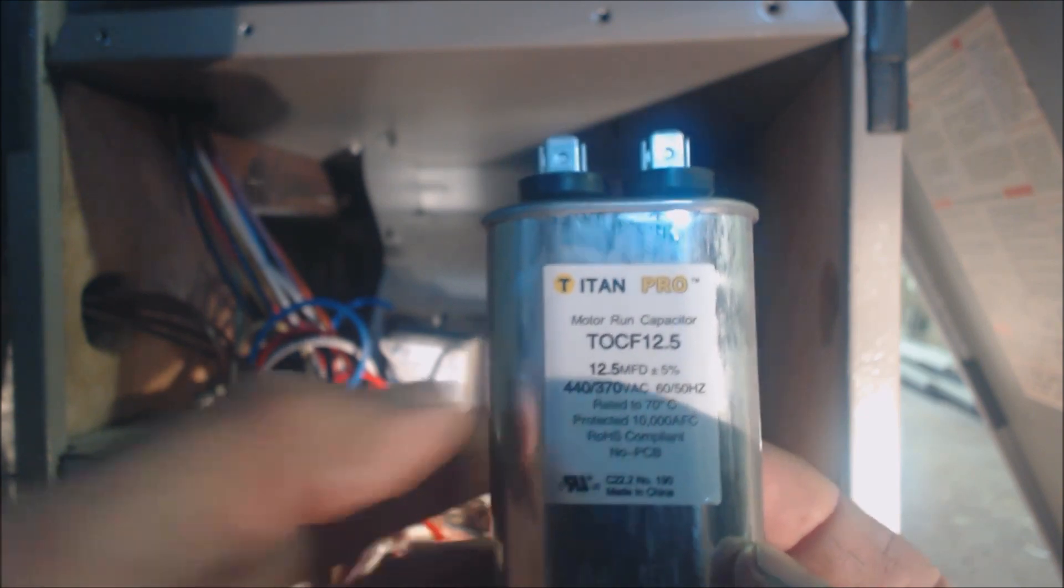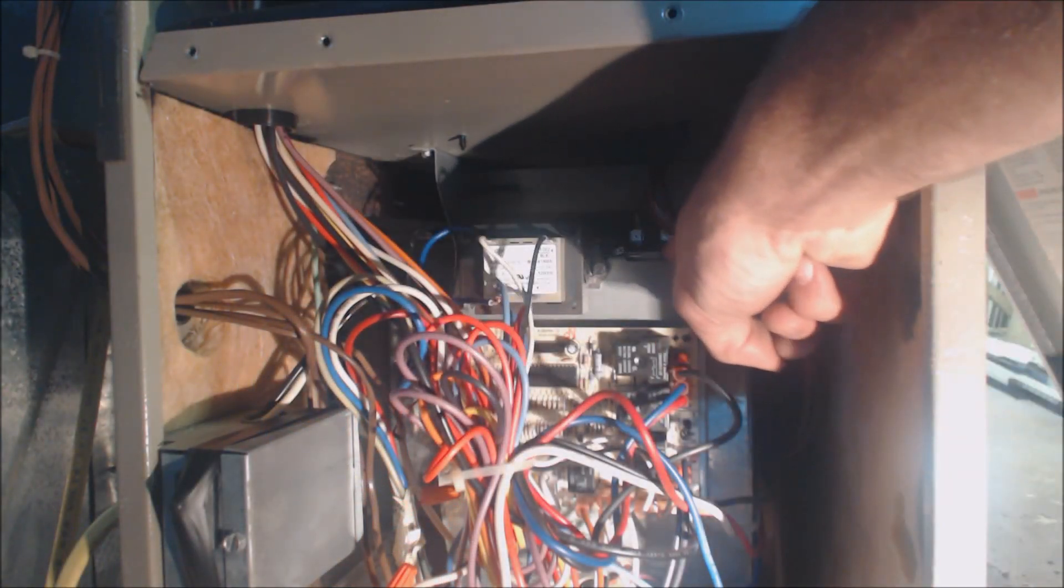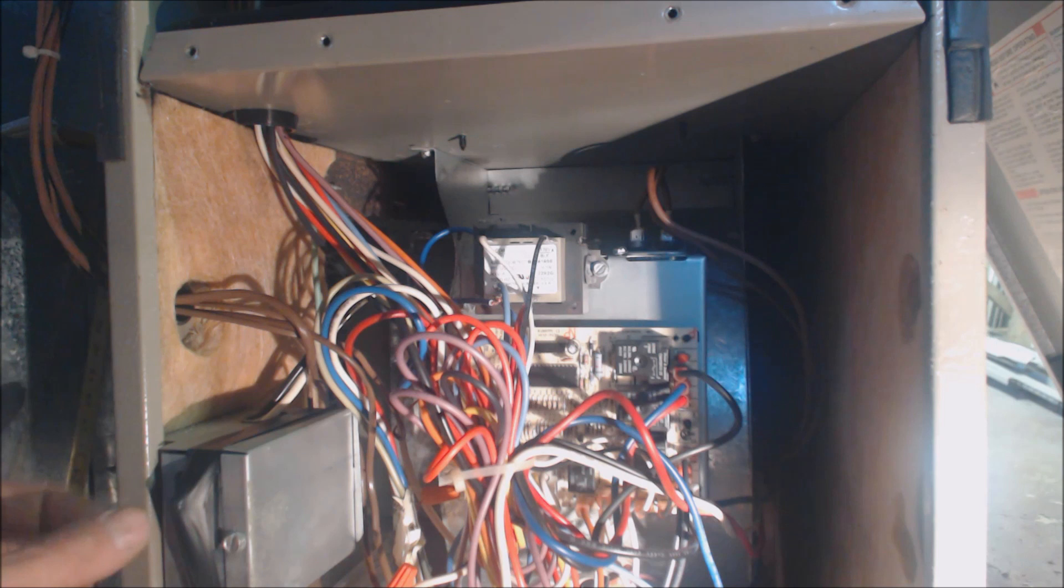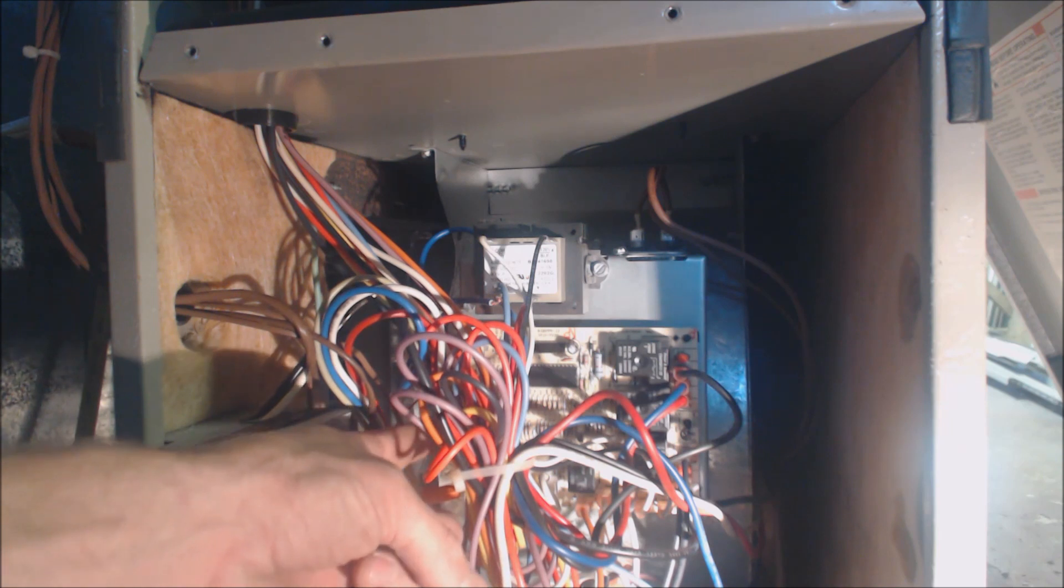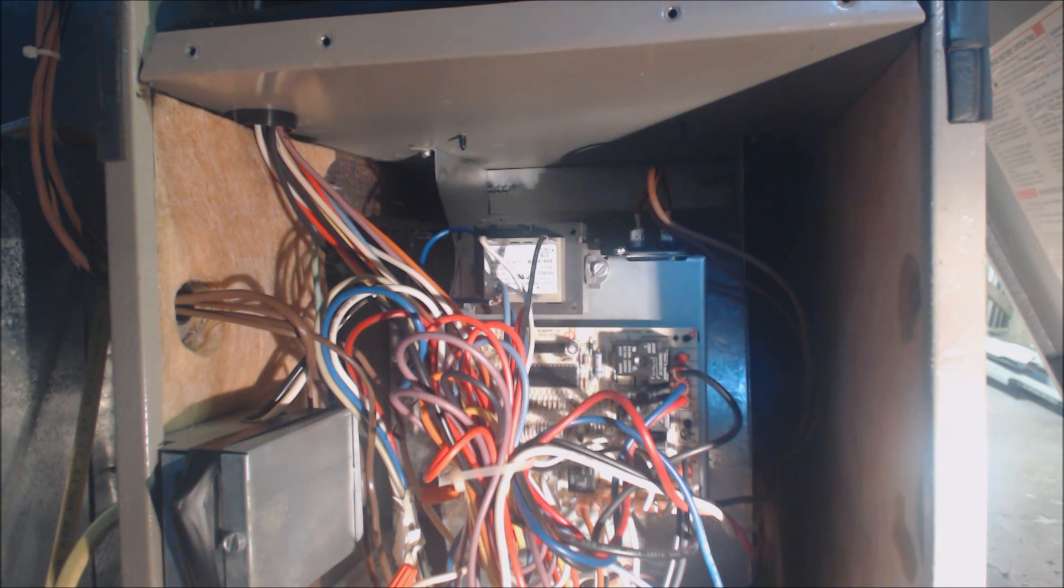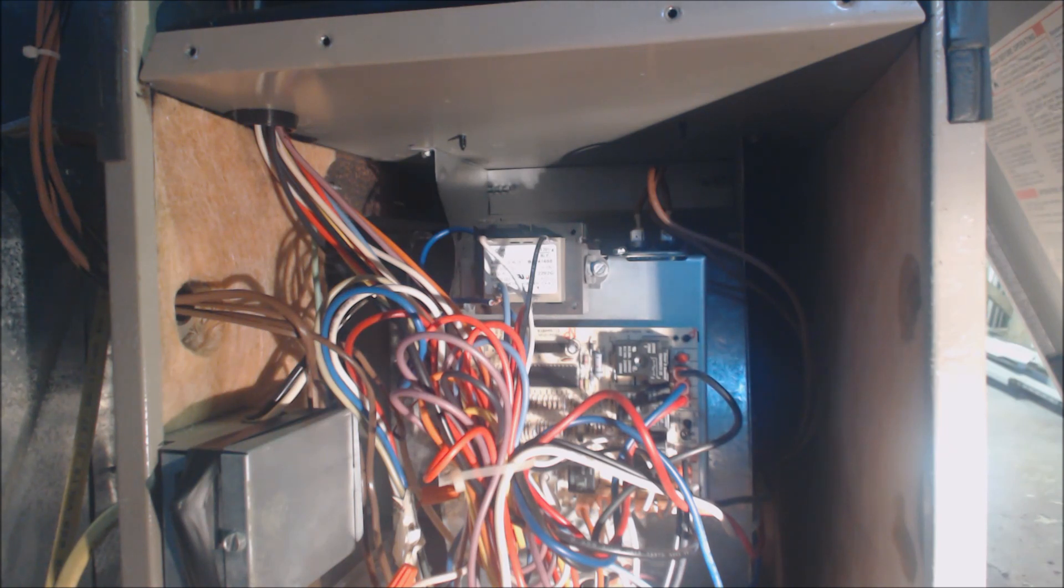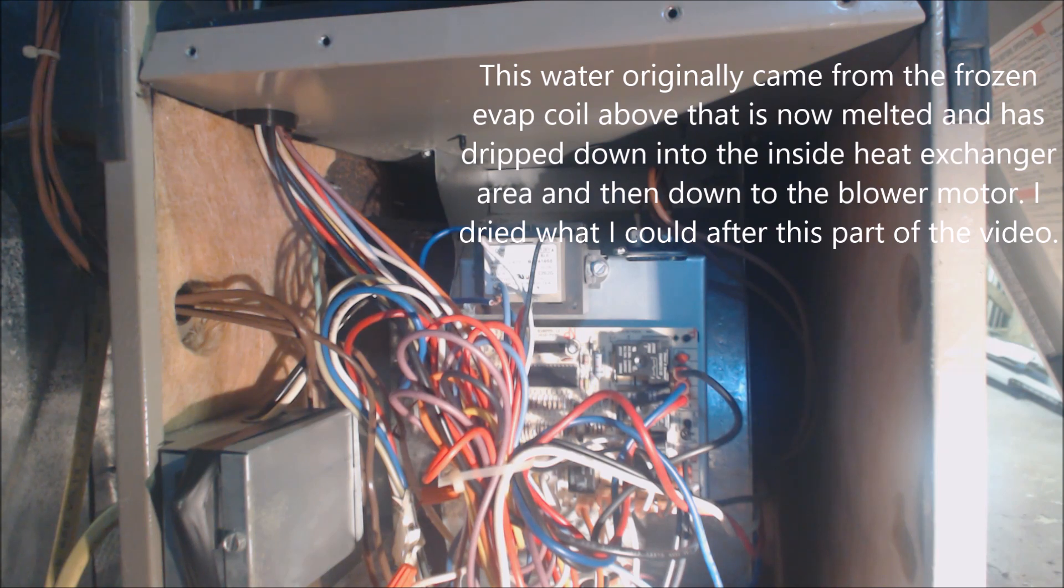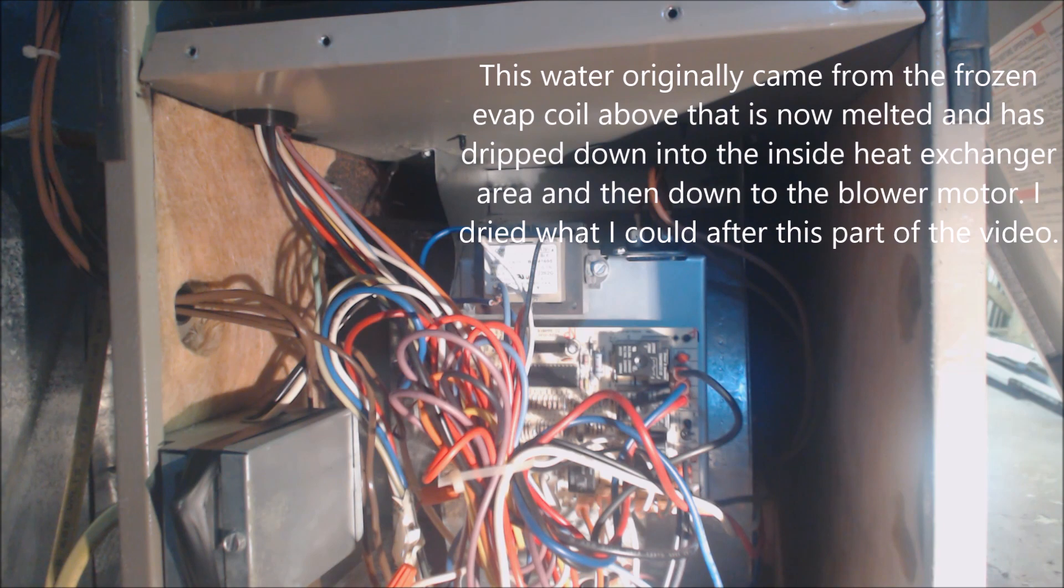The new capacitor is installed to the same mfd rating or uf rating as the old one. The door switch is actually taped shut because I can't use a magnet on this particular one. Now I'm going to go ahead and turn the power on. I did take the jumper out from R to G because I do have that calling on the thermostat presently. We just turned the power on and we should be getting a signal from R to G. There's the blower motor turning on. I am going to have to address this water coming down here, dripping from the top of the unit. That's not good. I've got to clean all that off. Hope you enjoyed yourself. We'll see you next time at AC Service Tech channel.